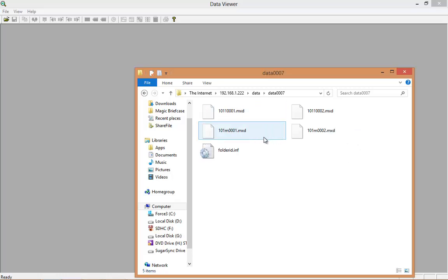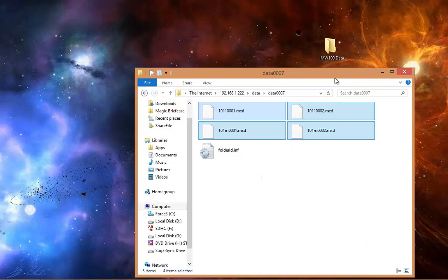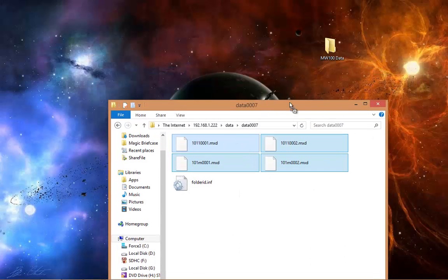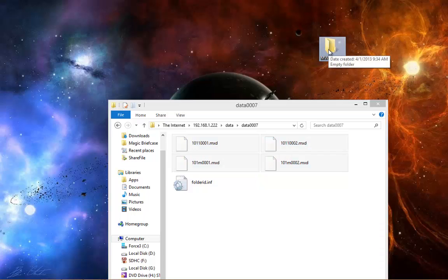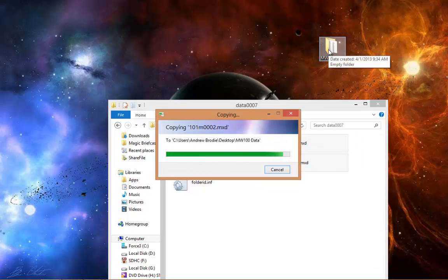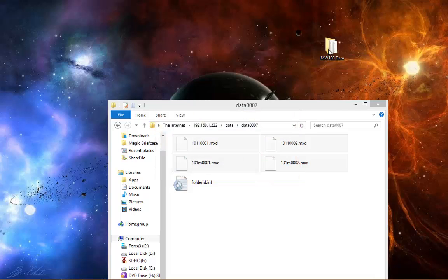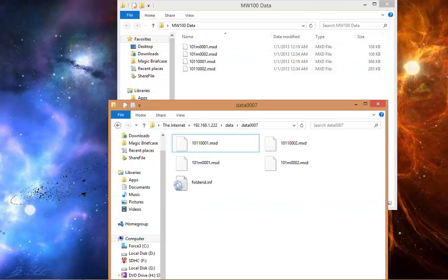And the ones that you're interested in are the MXD files. So the ones with M beside them, those are if I had math channels up and running on the MW100. So those contain the math data, and those contain the regular recorded channel data. So at this point, if I wanted to, I could just go ahead and select those, and I could copy them over to a folder on my local PC. So now I've moved those off the MW100 to a local folder on my PC. Okay, so there they are.